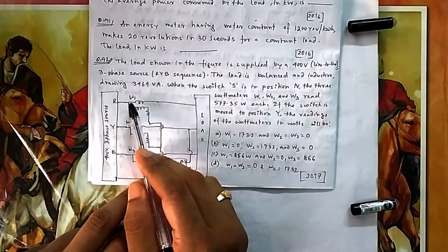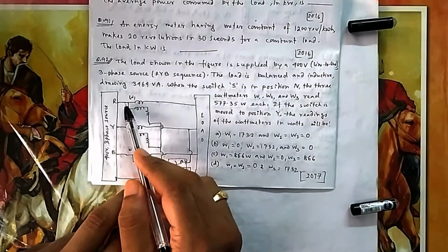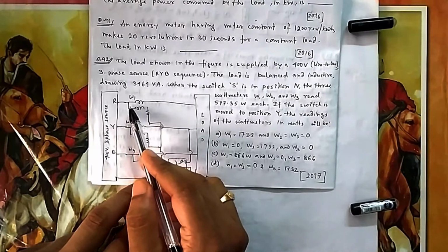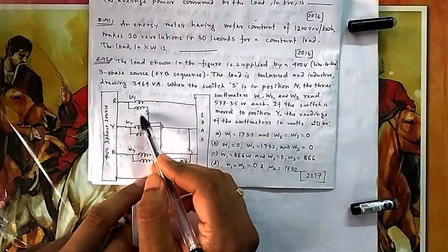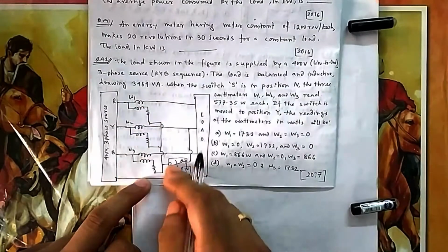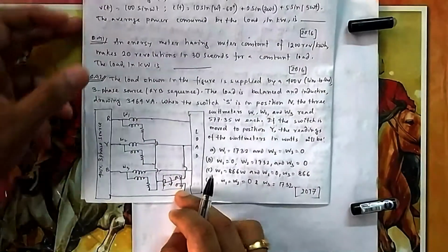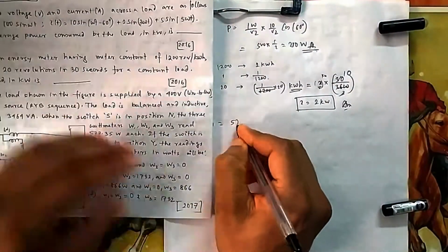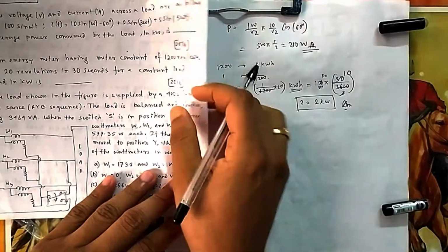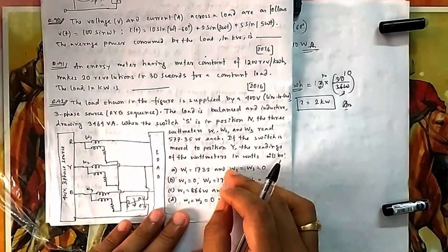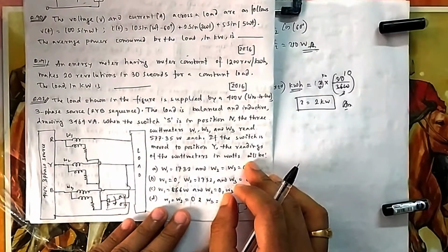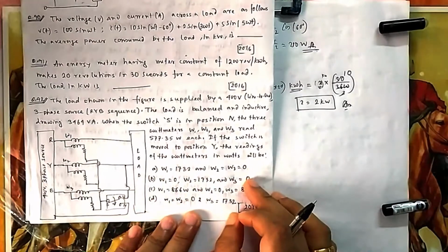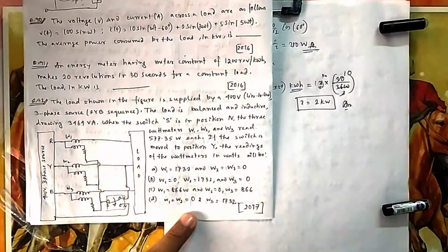That means if you take wattmeter 1, what it is calculating is the current through R phase and the voltage across R, that is VRN, the phase voltage VR, connected to N. So if you take all this, suppose wattmeter 1 I answer, how much is it reading? 577.35. So let me calculate what are the currents, angles, power factors, all these, then we will see where it is connected in Y, because the angles will be needed, what voltage it is measuring and what current it is measuring.